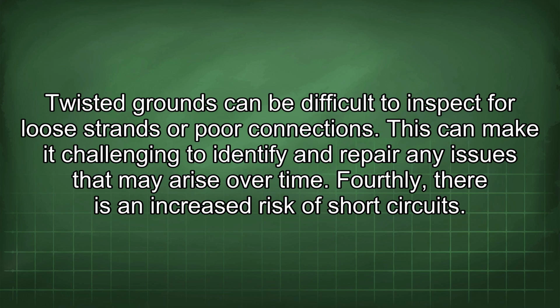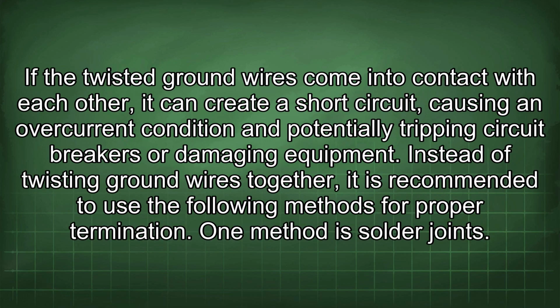Fourthly, there is an increased risk of short circuits. If the twisted ground wires come into contact with each other, it can create a short circuit, causing an overcurrent condition and potentially tripping circuit breakers or damaging equipment. Instead of twisting ground wires together, it is recommended to use the following methods for proper termination.